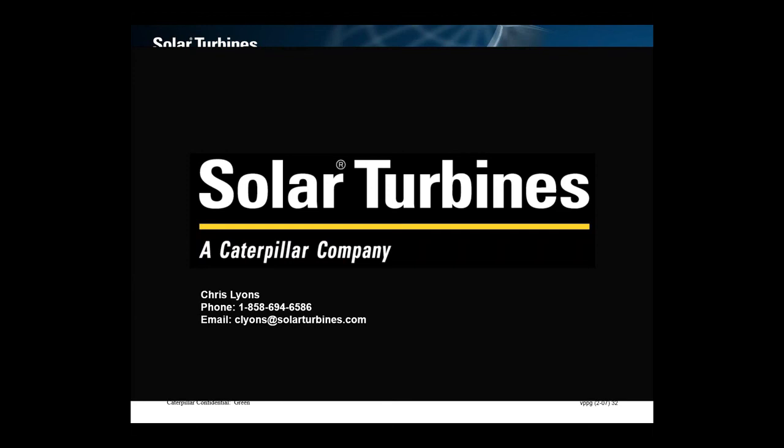Gotcha. And then the final question before we turn it over to Mark is, when combusting landfill gas, how do you deal with siloxane removal, and what's the cost? That's a good question. Siloxanes are a silica that's in everything from shampoos, deodorants, and things like that. It's in the gas, and when you combust it at high temperatures, it melts, and then as you cool the gas in the gas turbine, it solidifies on the turbine blades.